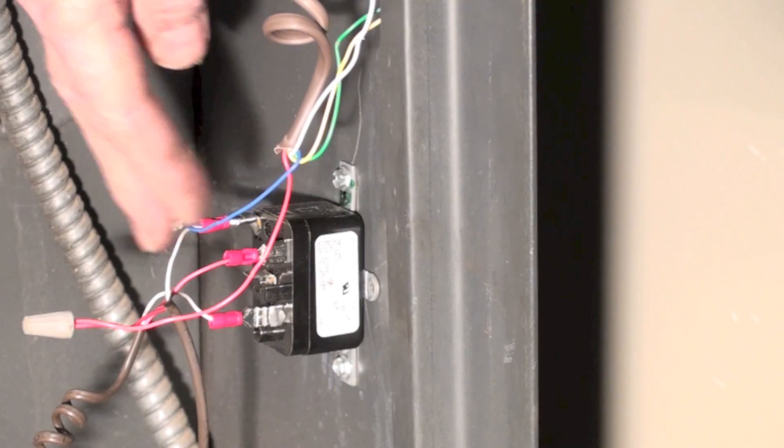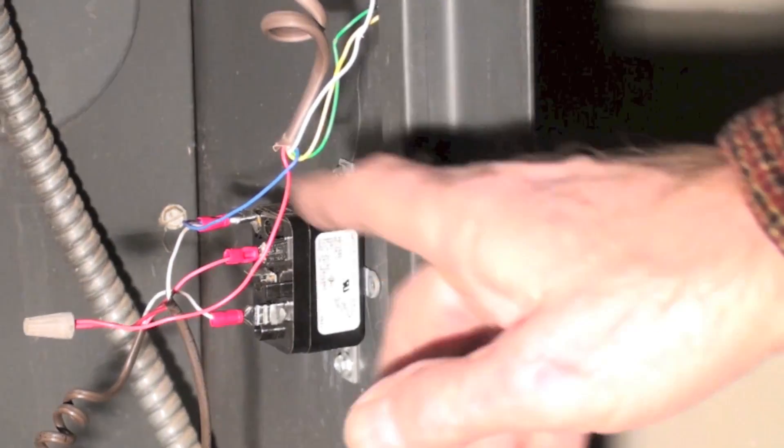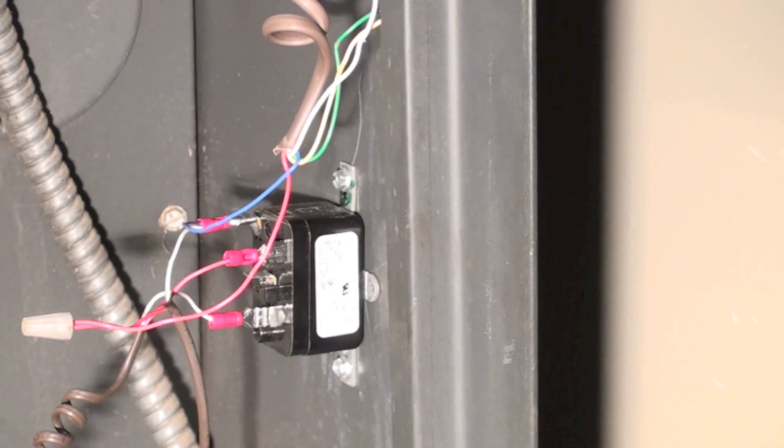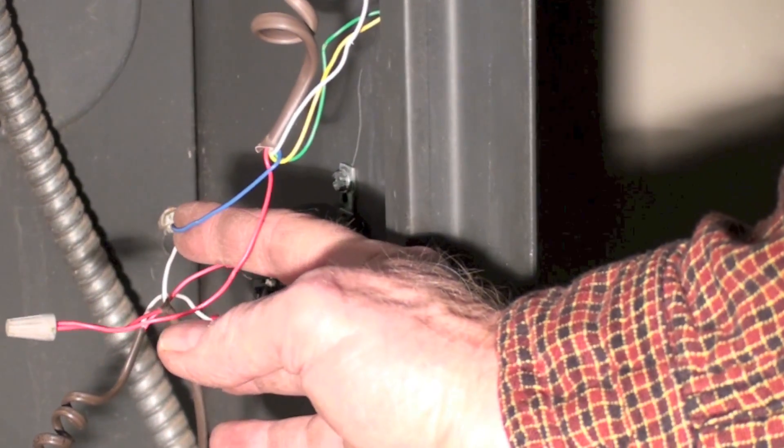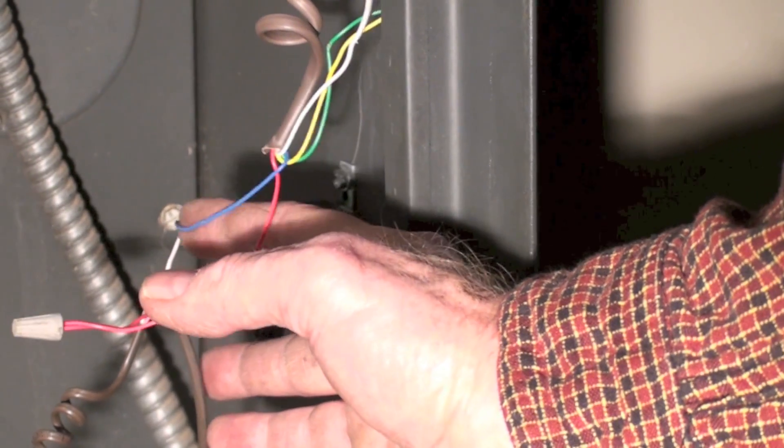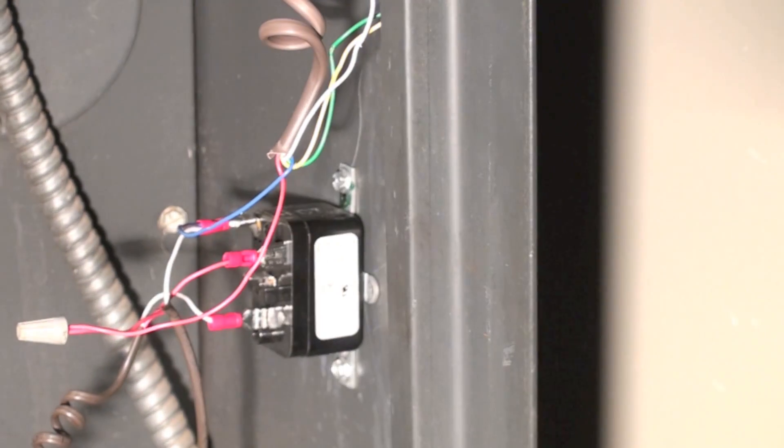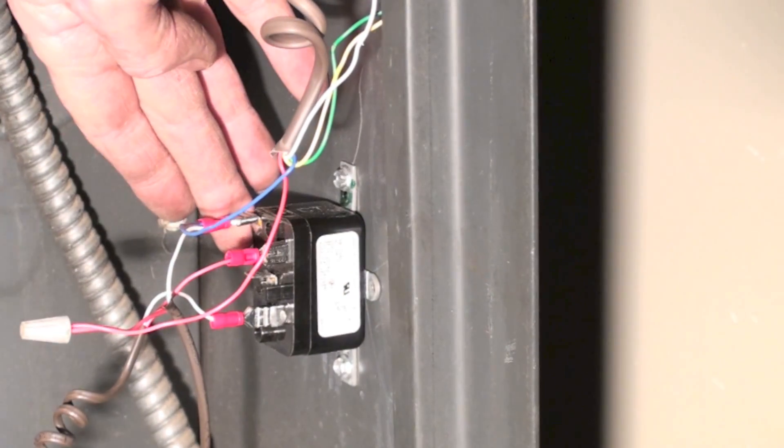And I've also got from that white, I've also got a common going up to the thermostat. This is where we're going to get the common going to the thermostat. I've used blue because I've got a green, I've got a yellow, I've got a white, and all those are going to be for other things. So I'm going to use the blue for common, so it's feeding the coil of this relay.